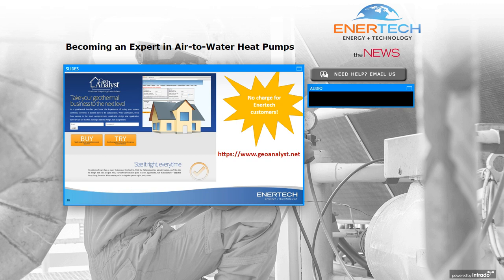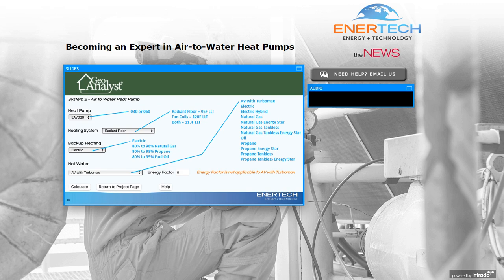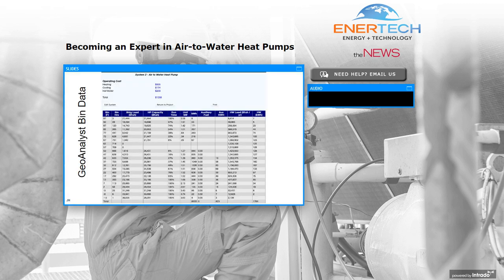The software GeoAnalyst is what we use to actually calculate those graphs that Tim was showing. This allows you to put in your heat loss, heat gain calculations, and then you can choose the system that makes the most sense or multiple systems so that you can compare what works the best in your particular area. The air-to-water unit has a special setup for selecting the size of the equipment, the type of system that you want. Is it radiant floor, fan coils, or both? What type of backup heating are you going to use? And what type of domestic hot water? Once you choose those and you have your heat loss, heat gain calculated, then we can get some actual operating costs. It can be kind of confusing when we have COPs and HSPFs and AFUEs, but if we plug that information into GeoAnalyst, it will give us dollars rather than all those different ratings.